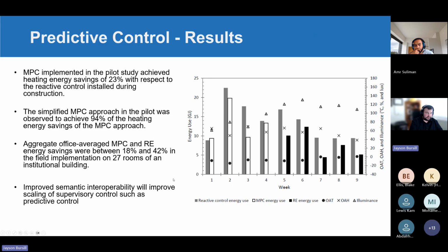So all these different predictive control modes, whether full predictive control or this simplified rule extraction, ended up being between 20 and 42% energy savings. This number probably would scale down because this particular building had a 24/7 schedule when I was experimenting on it, and there were a few other inefficiencies in the building. I think even without a 24/7 schedule, you could probably cut this in half, down to something like 10 to 20%, which is very real.